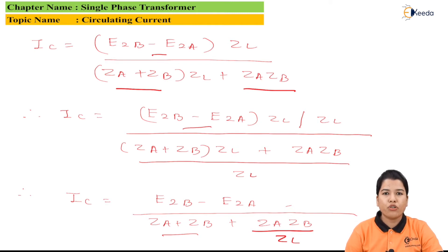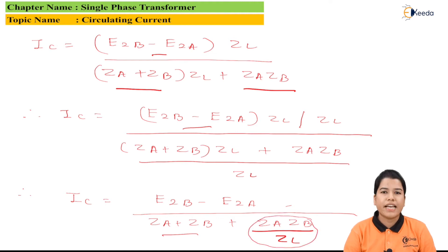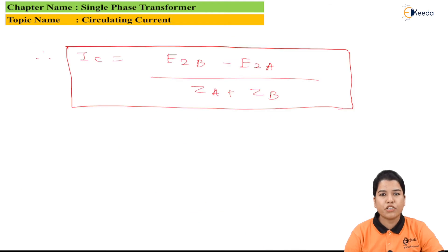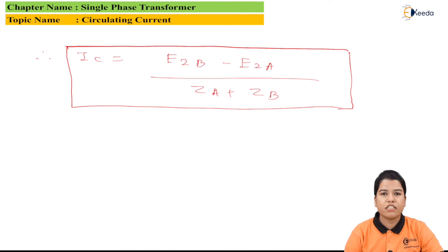At no-load condition, the value of ZL is infinity. Hence the final formula for the circulating current is: IC = (E2B − E2A) / (ZA + ZB). This is the formula for the circulating current.